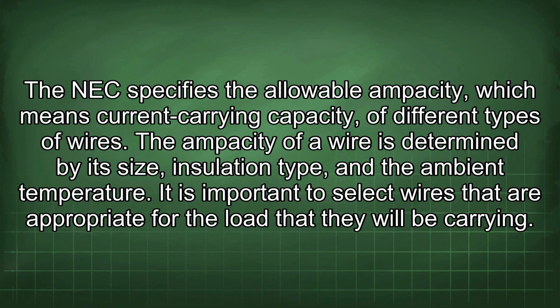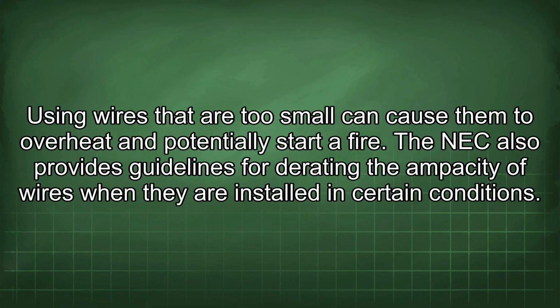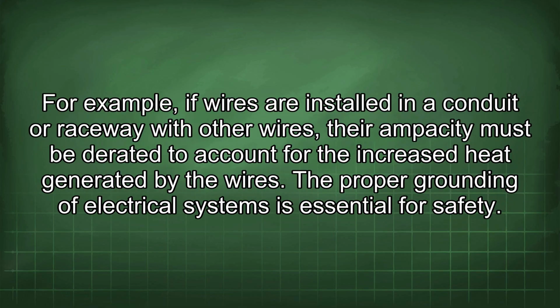It is important to select wires that are appropriate for the load that they will be carrying. Using wires that are too small can cause them to overheat and potentially start a fire. The NEC also provides guidelines for derating the ampacity of wires when they are installed in certain conditions. For example, if wires are installed in a conduit or raceway with other wires, their ampacity must be derated to account for the increased heat generated by the wires.